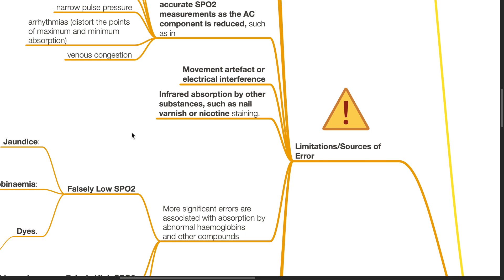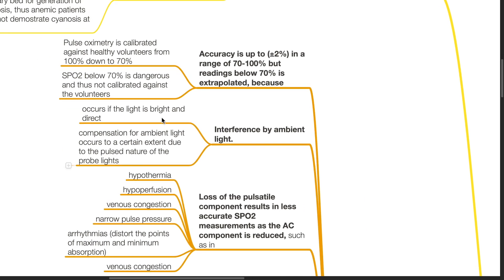Limitations and sources of error for pulse oximetry. Accuracy of pulse oximetry is plus or minus 2% in a range of 70 to 100%, but readings below 70% are extrapolated, as pulse oximetry is calibrated against healthy volunteers from 100% down to 70%, and saturations below 70% are not conducted in healthy volunteers as it is dangerous and unethical.